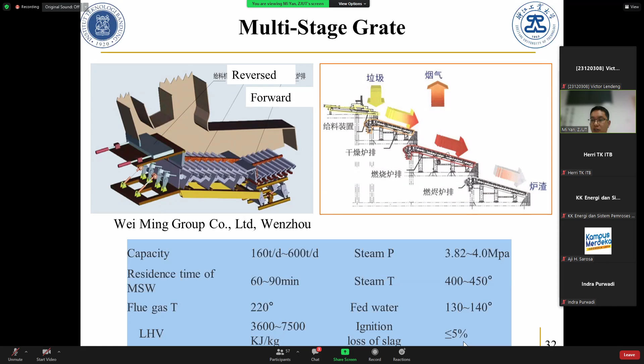The flue gas temperature is 220. So I have to explain what flue gas means. Flue gas temperature means after all the heat exchangers, usually after the air heater or after the economizer. And the feeding water is 130 to 140. So this is also designed depending on the economizer. The ignition loss of slag is smaller than 5%, which will be used to calculate the combustion or incineration efficiency.